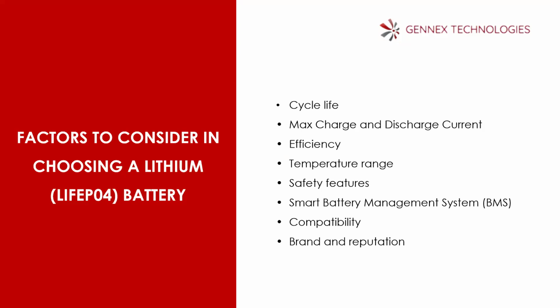Another point is max charge and discharge current, which is always high, so you need to look at that too. Because of your application, if you want to power a pump that demands a startup current higher than your battery can handle, the battery will shut down when the load is about to start, and this is not professional. So look at the maximum current rating, so the battery can withstand the surge current demanded by the load. Very important.